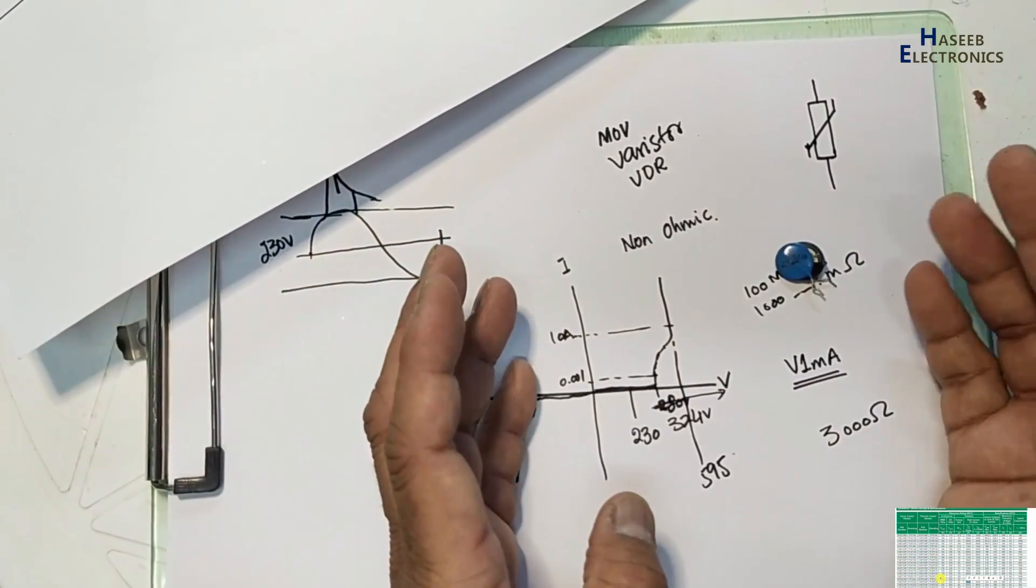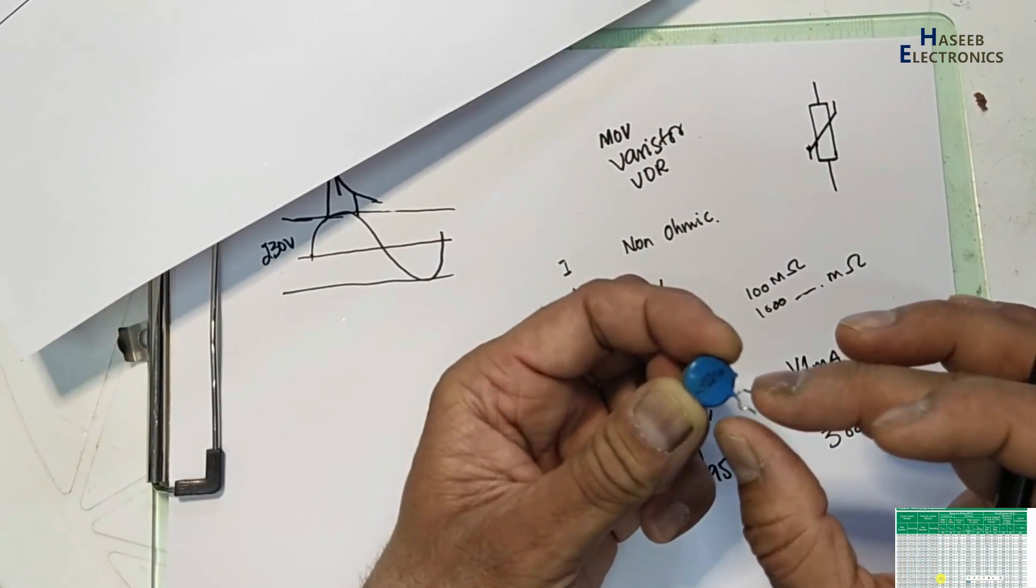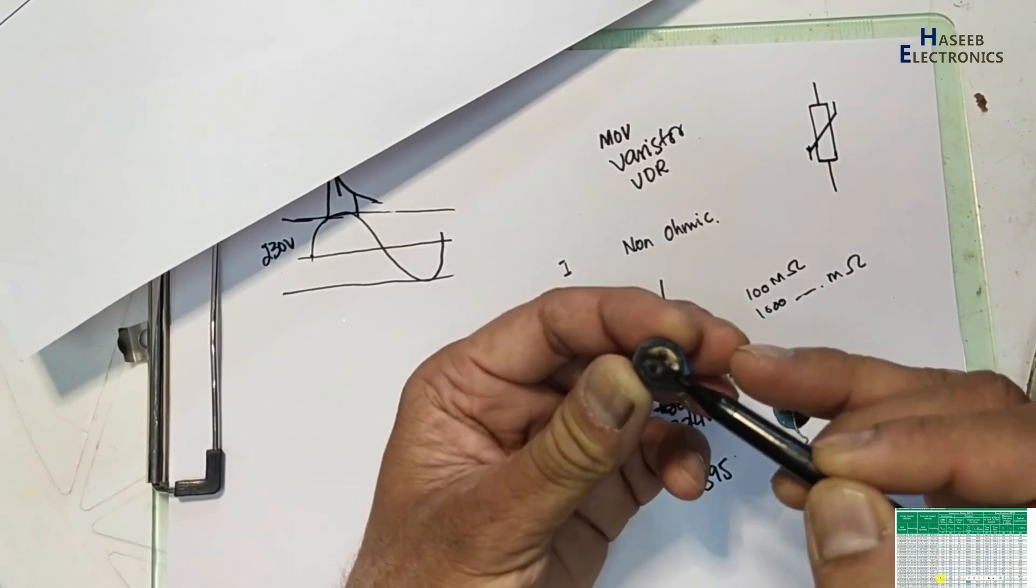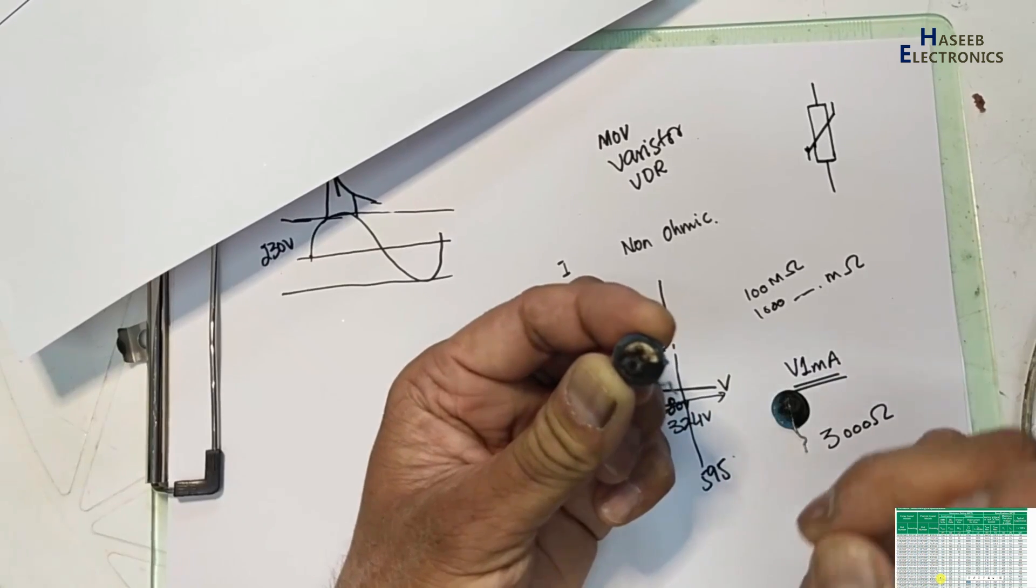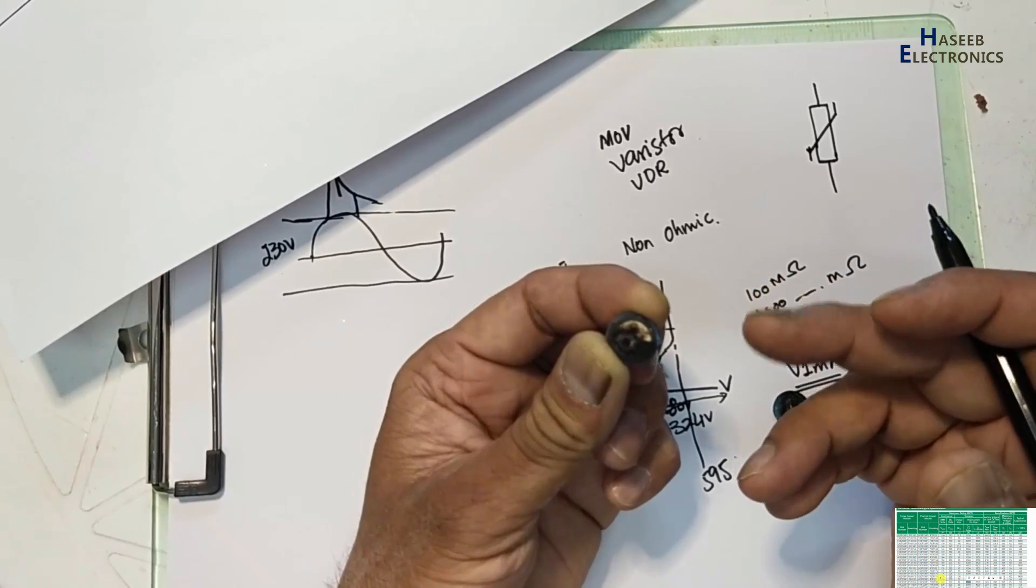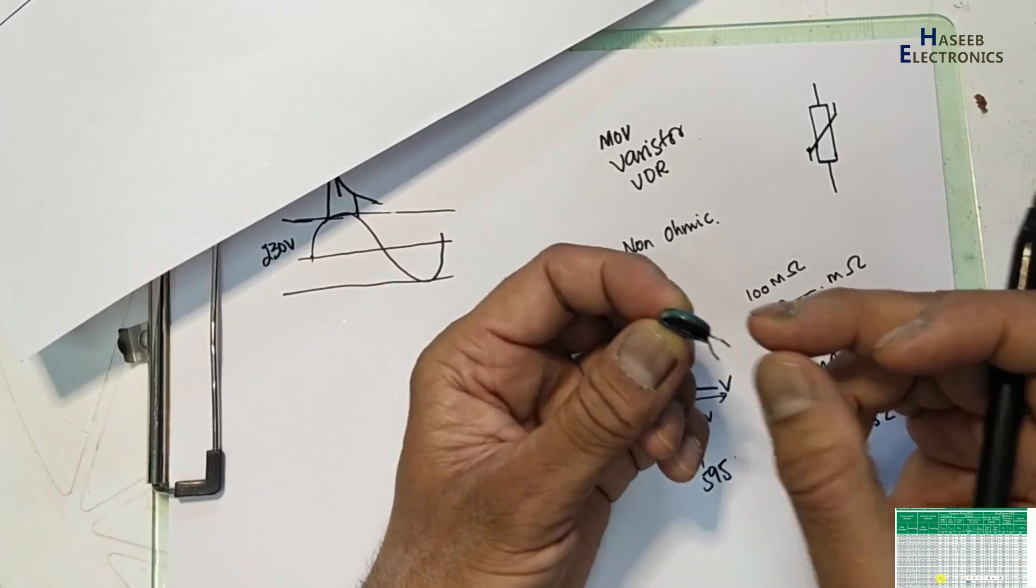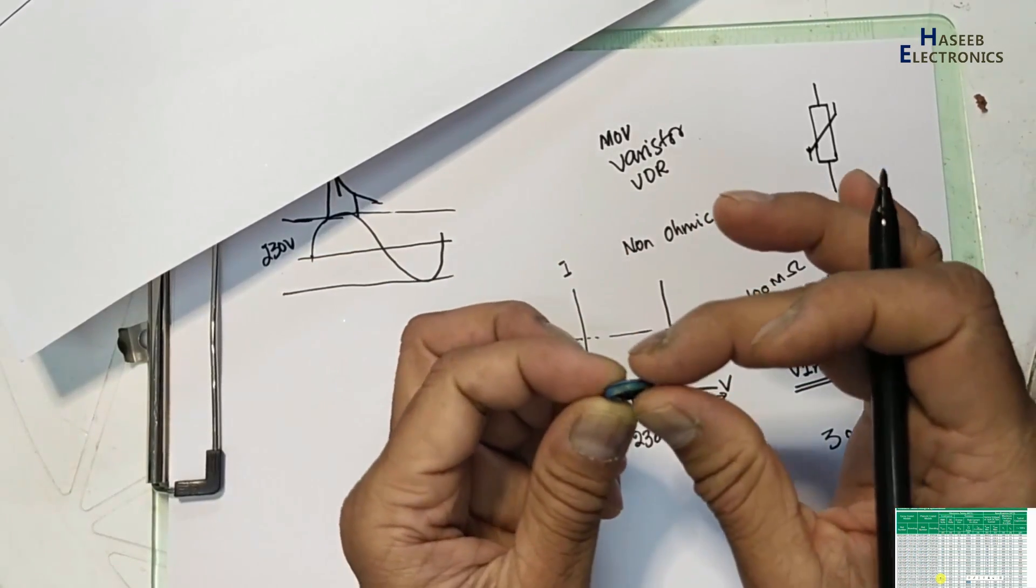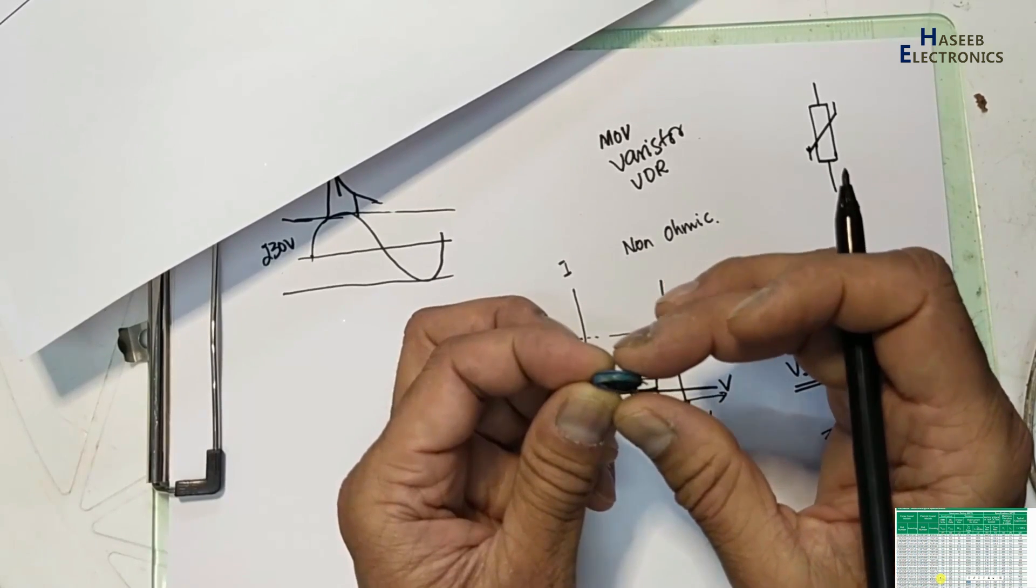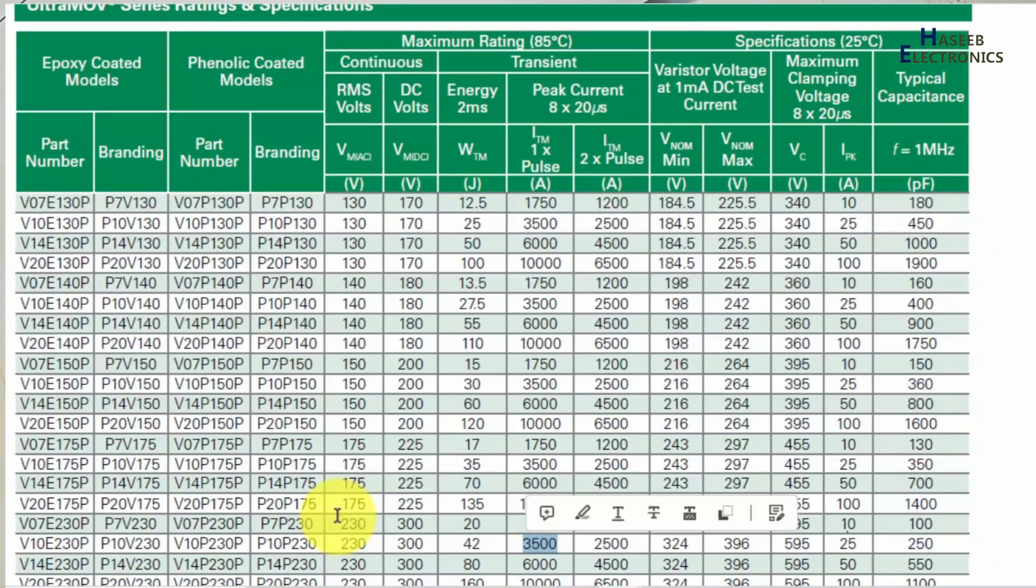Now if we are selecting any MOV, any varistor - if we need more current, this MOV comes in disk sizes. That is this disk size - it is in millimeters: 3 millimeter, 5 millimeter, 7 millimeter, 10 millimeter, 14, 20. Each disk size has its own current level. Then if we need more voltage, at that time its thickness will increase. More thick, more voltage. Larger disk size will handle larger strike.